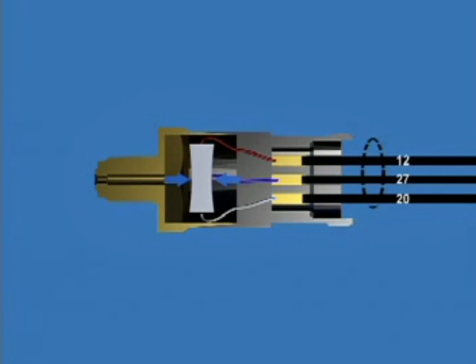These sensors contain a crystal structure. Pressure compresses the crystal, creating a small voltage proportional to the amount of pressure. This is known as the piezoelectric effect. With this type of sensor, the resistance can be measured to verify proper operation. However, the resistance range is too large to verify sensor calibration with the resistance check. The sensor calibration is checked by comparing the reading in Insite to the reading on a mechanical gauge.